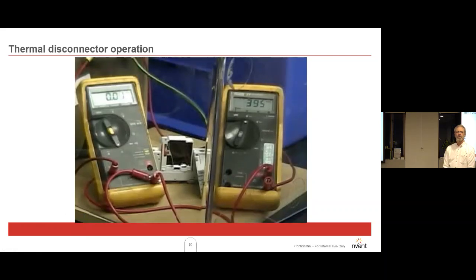Right, the voltage is rising, and you keep watch out for the smoke in the middle. And that's a spring-loaded fuse inside, trips and disconnects them off. So that's the internals, and that's for internal protection to prevent this from going up in smoke. It is not the same as the external fuse, which is needed to protect the wiring going to the surge protection device.